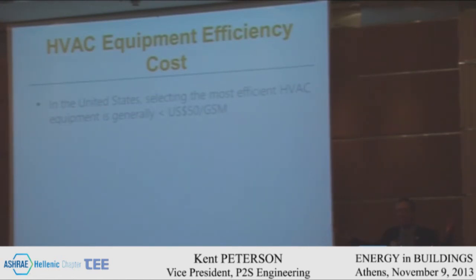That cost covered all equipment, from air handlers to chillers, including oversizing the air handlers for lower face velocity, reducing overall static pressure, and going to the highest grade efficiency chillers and cooling towers. This translates to about $5 per square foot. In the U.S., the General Service Administration is probably spending closer to $25 per square foot just on the marble in the lobby, so we need to put this cost in perspective.